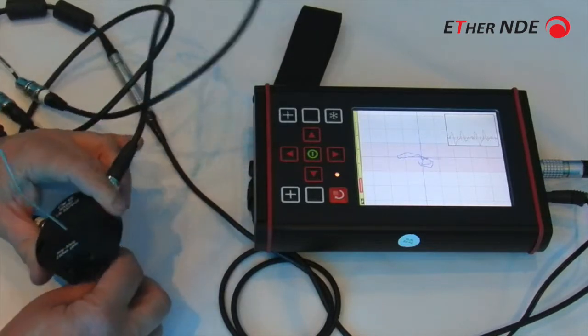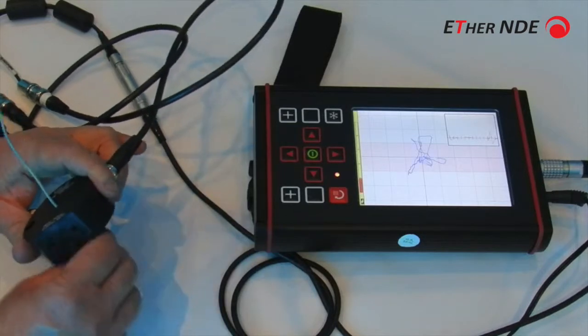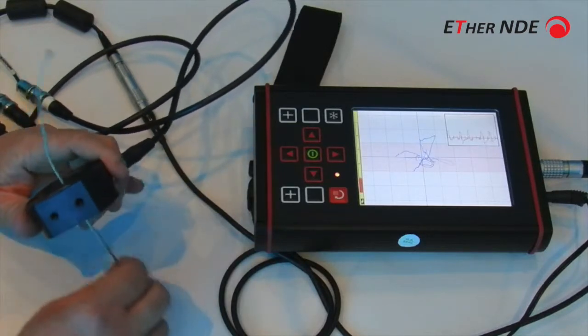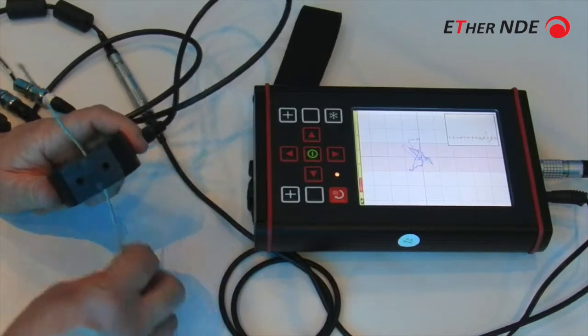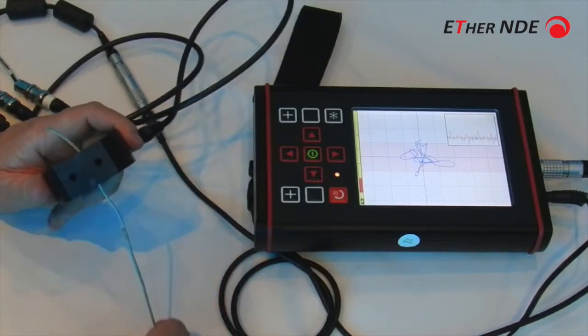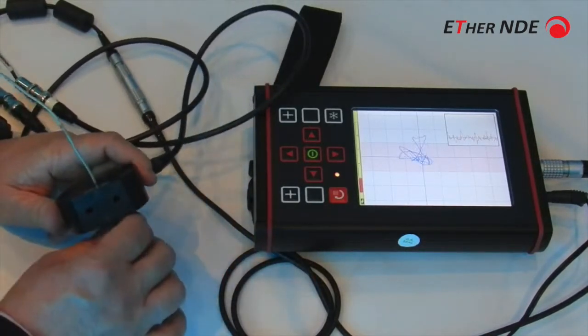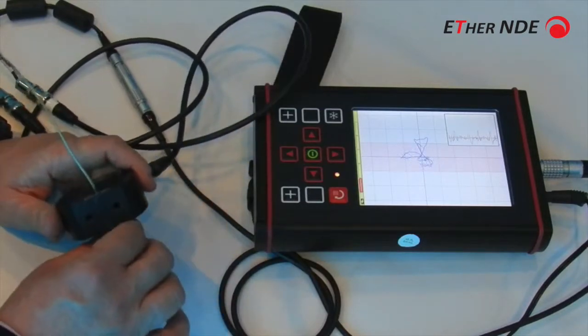Coils are available in the 2.6mm, you can go down, test everything from wire, to tube, to bar, etc. in non-ferrous materials, for surface defects, and if the frequency is low enough, for internal defects as well.